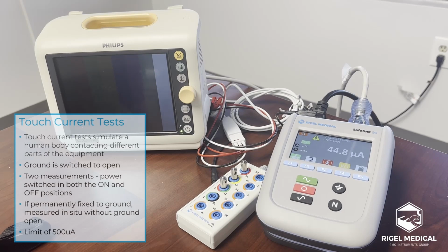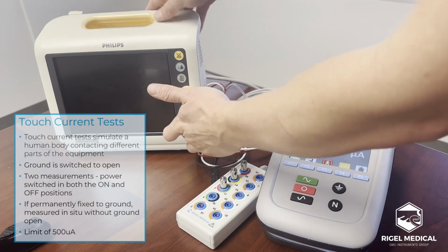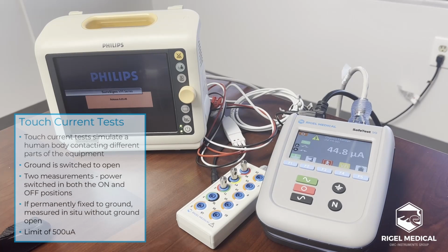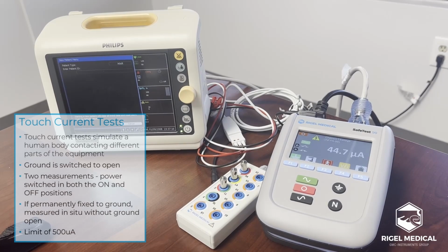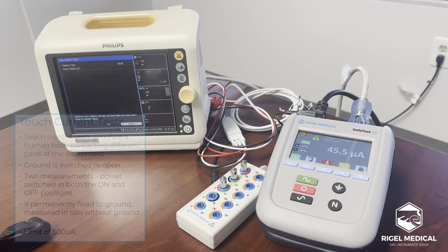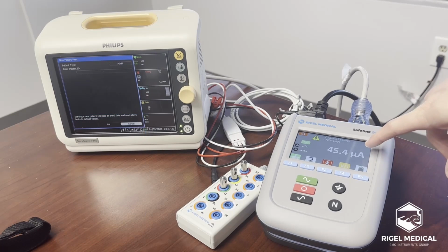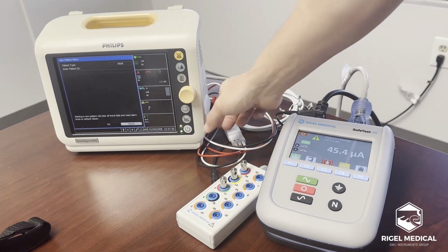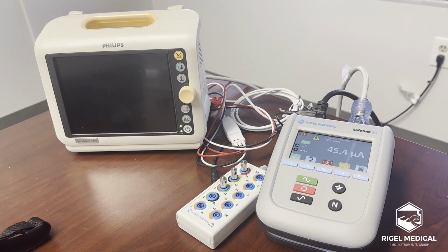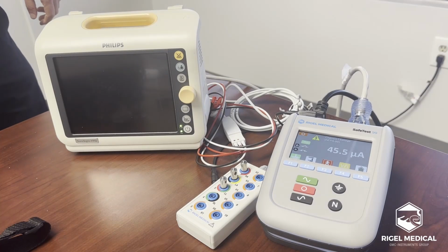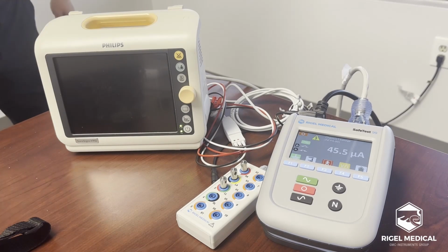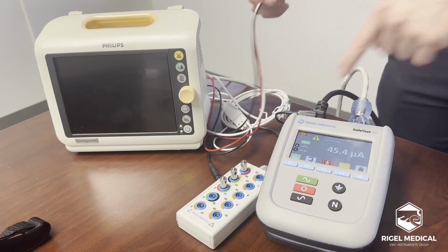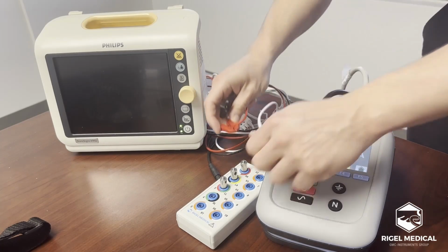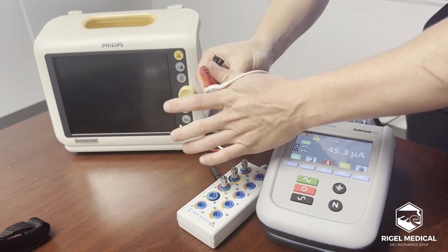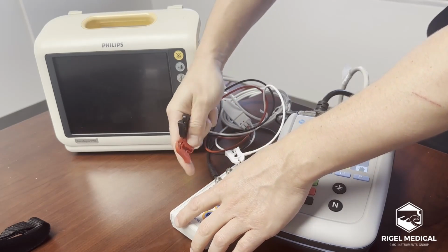And it should be in both the on and off positions. This power switched in the on and off, so I'll switch this device on. And I take 2 different values once the device is powered up. Okay, slight increase in the leakage values there, but still below the limit of 500 microamps. So I'm happy with that. And then we can move on to the next test, which is the lead leakage current tests. So I've got my ECG connections here. I've already got some snap adapters in the box, so I can connect each of those. It doesn't really matter the configuration of where these go, because we're just performing electrical safety.